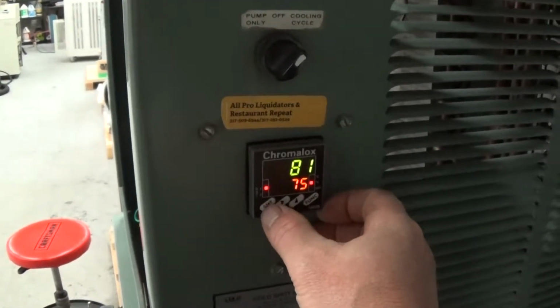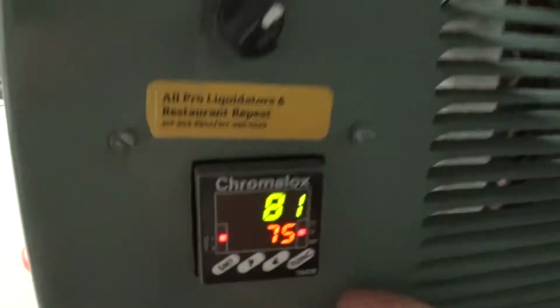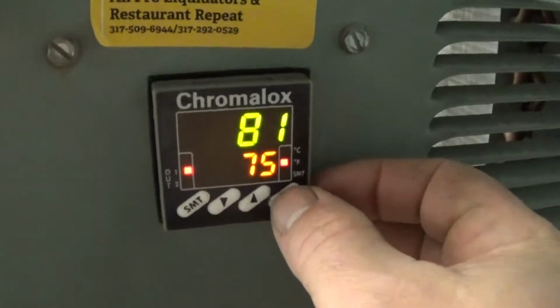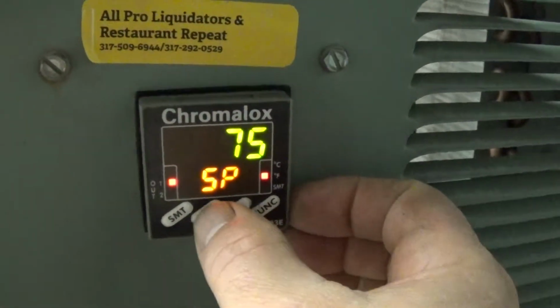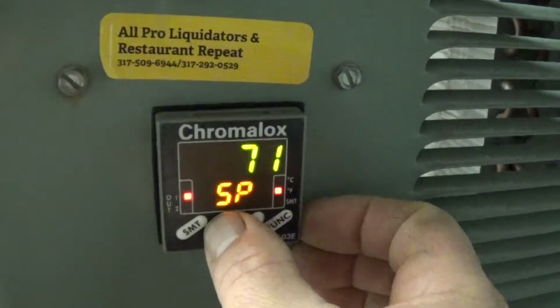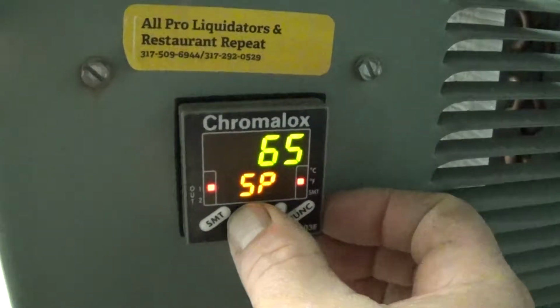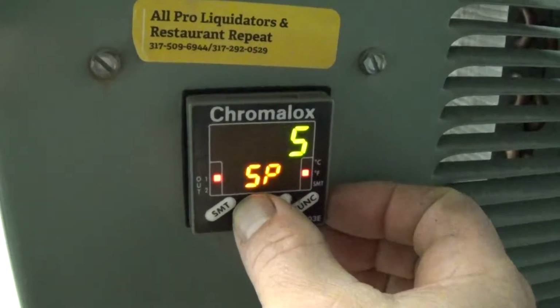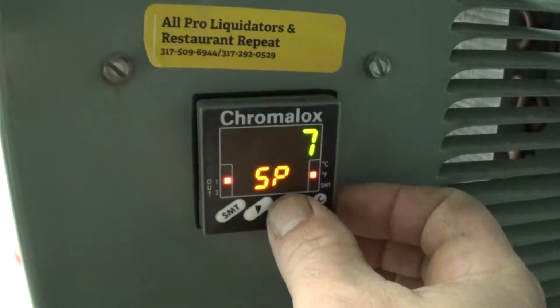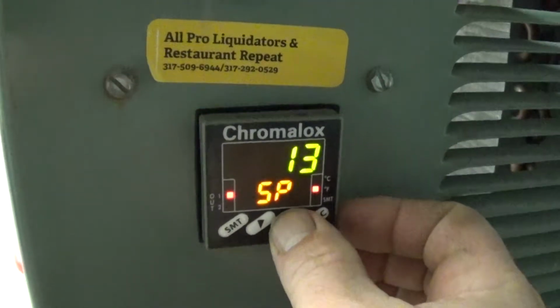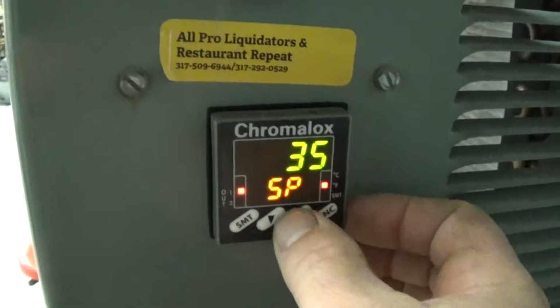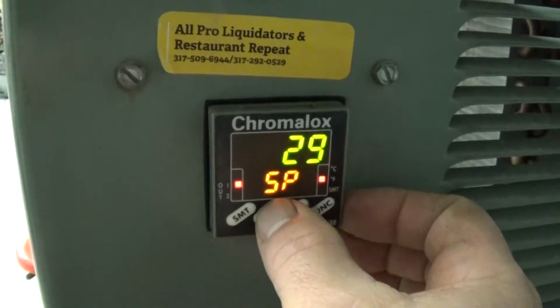You don't have to worry about SMT, which is smart test. When you change the set point, you just have to simply press function, set point 1, or set point, and just press the down key. And for brewery chillers, most people want to set it at 28 Fahrenheit, give or take. And we've gone through this, done a couple things. We'll talk about those in a minute.